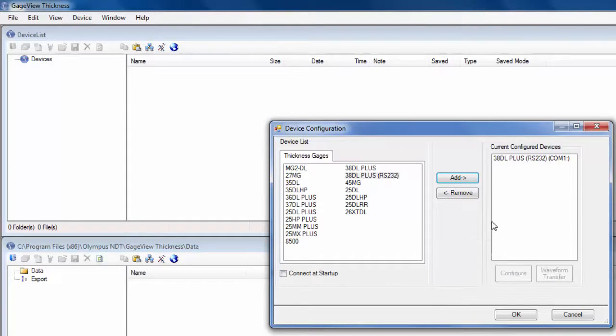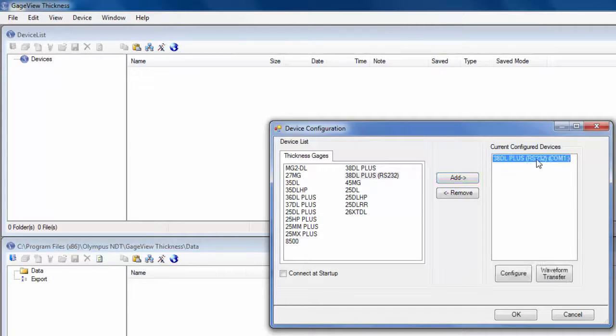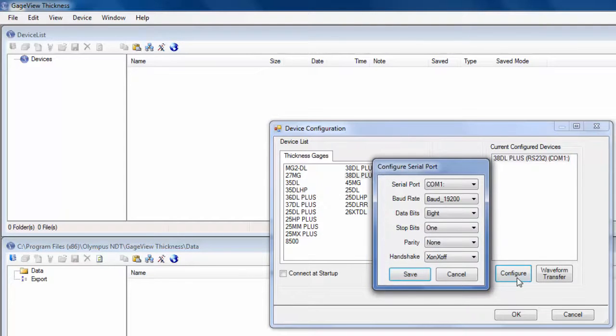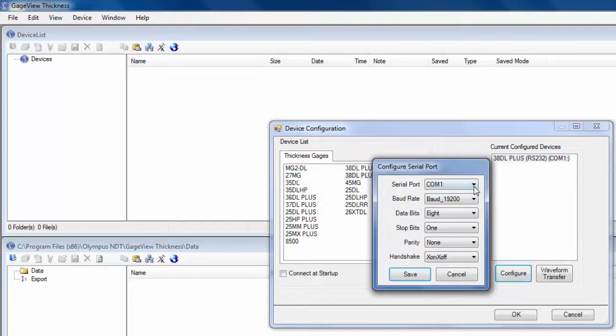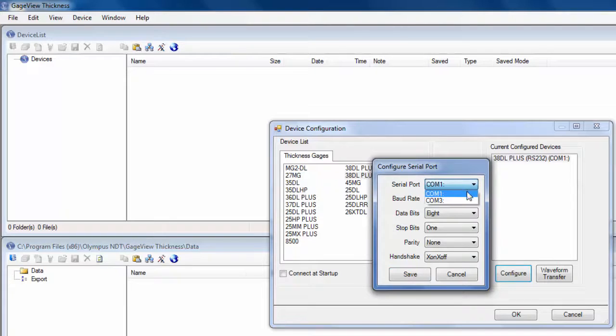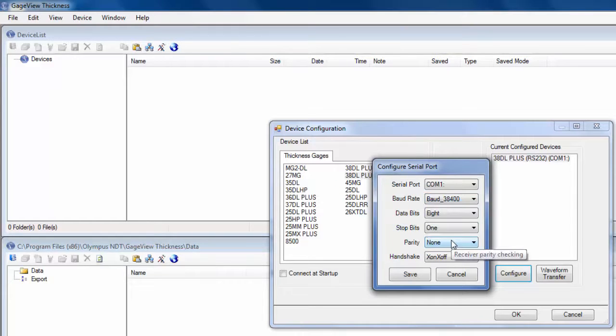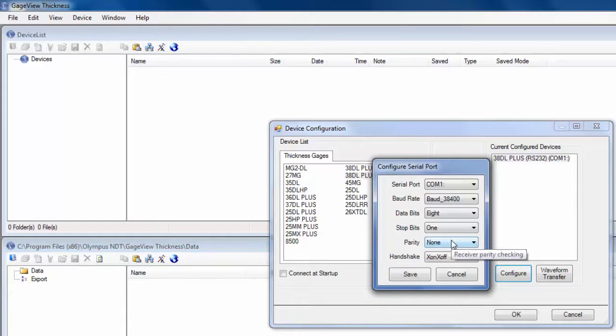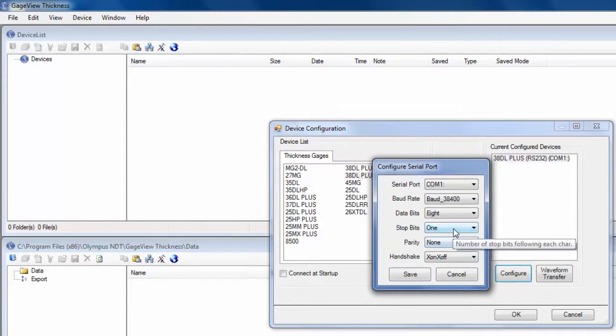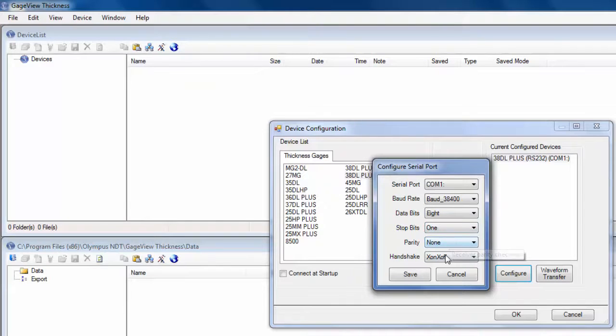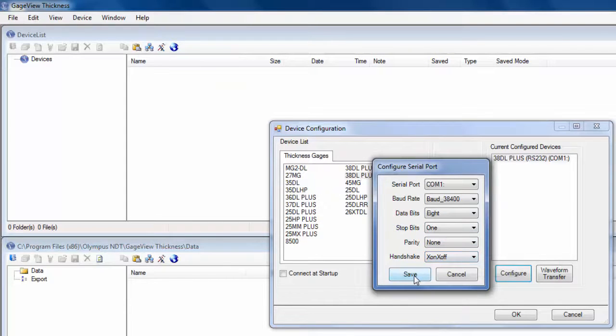To configure the instrument, since it's RS-232, we need to click the instrument and then click Configure. Here I choose my COM port, I'm using COM1. My baud rate I change to 38400. Then typically we keep DataBits 8, StopBits 1, Parity None, and Handshake XOn XOff. Then you can click Save.